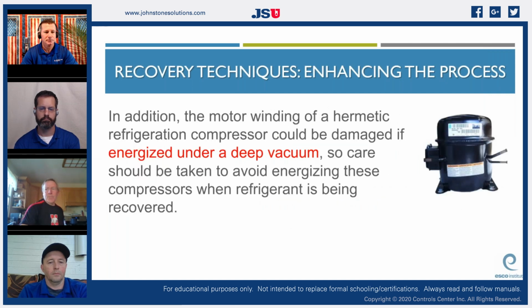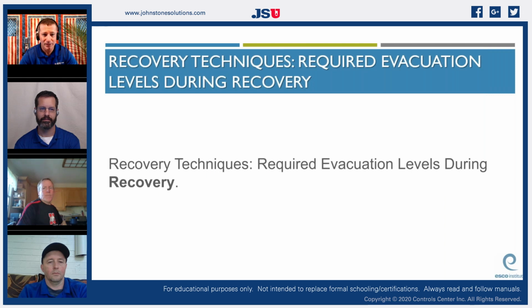So I had this happen actually last year, I think, Clifton, you'll remember. A guy made a repair on a service valve, pulled what he told me was a 300 micron vacuum, and he turned his system on in a vacuum. He said it had to be running to weigh the refrigerant back in. I'm like, no, it didn't. You're already in a vacuum. You should have weighed it in through the liquid line as it was in a vacuum. So he actually tore his compressor up. I mean, trashed it. Yep. He put 240 volts to it under a 300 micron vacuum, and I saw what it did to it. Well, it's like when we talk about older televisions and amplifiers, where we increased our power by running it through a vacuum tube. Wow.